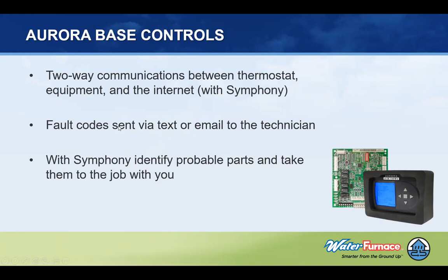It gives you fault codes via text and email to the technician. So even with a base control system, we can identify a probable part that you need to go out and troubleshoot a system before you go out. For example, if you have a high pressure lockout on a system that's in heating, lots of times you can just take a guess and say, it's probably a dirty filter that I need to go out and change.